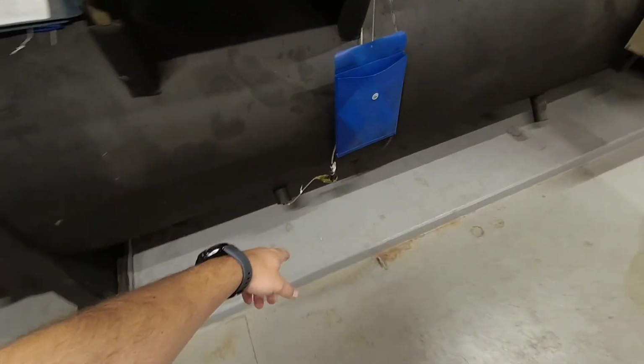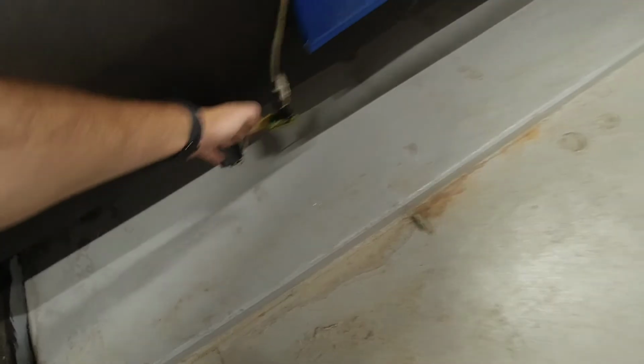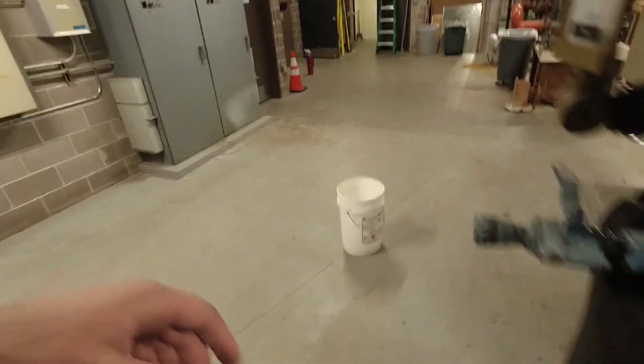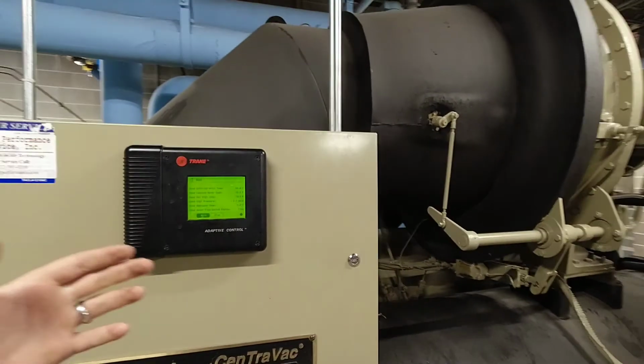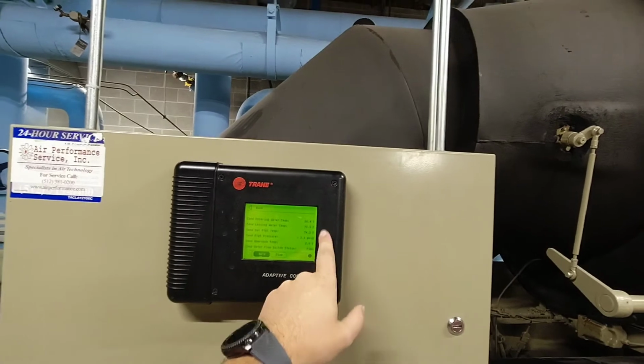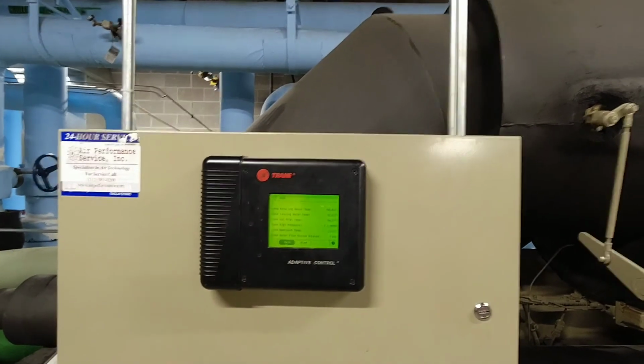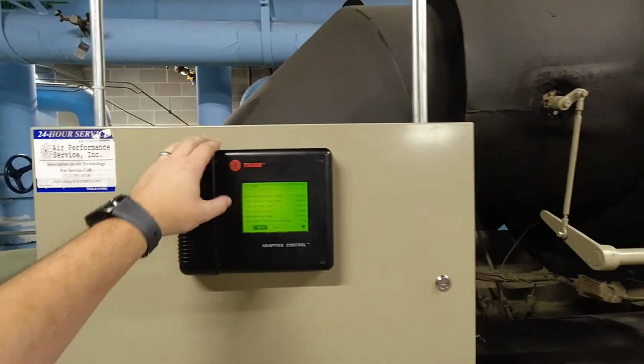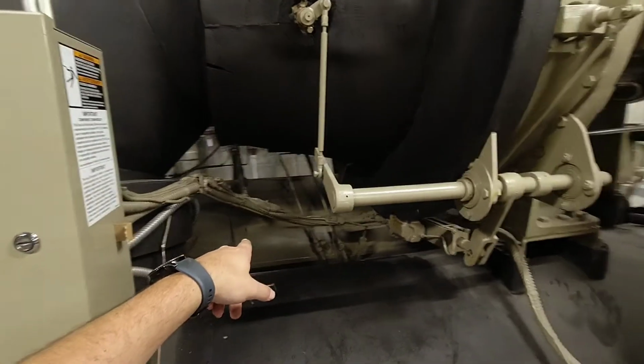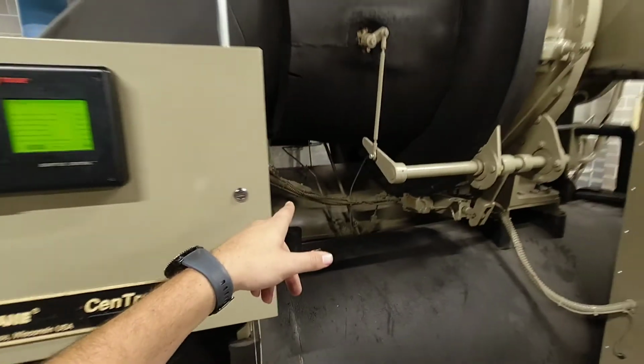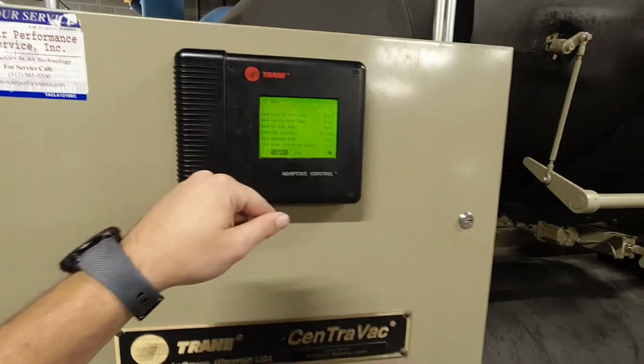Those pressures are conversions through temperature sensors. So this is your evap temperature sensor, and you can't see it now, but up under here on this particular series, in the liquid line is your condensing or condenser refrigerant temperature. A lot of times, especially when you start seeing surging, you won't see readings on the display that indicate why it's surging. That doesn't make any sense. That's because if you actually put a pressure gauge on it, you will find that the actual pressure is very different than what the display is telling you.